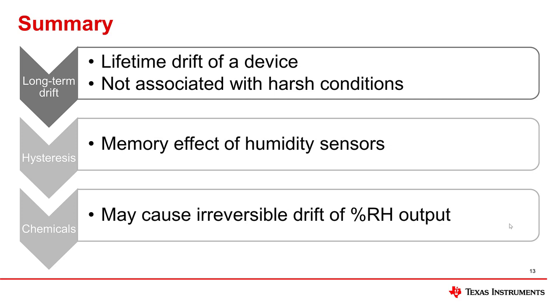To conclude, there are several main components of a humidity sensor datasheet accuracy specification. The long-term drift is usually defined in the datasheet as a percent relative humidity per year, but this assumes normal lifetime conditions. Hysteresis is also defined in most datasheets and causes the accuracy to have an offset that is dependent on the previous relative humidity reading. Chemical exposure cannot be defined in datasheet limits, but the sensing polymer can experience permanent positive or negative percent relative humidity shifts if exposed to chemicals during manufacturing or assembly, and it is important to take the necessary precautions when using an open cavity humidity sensor.